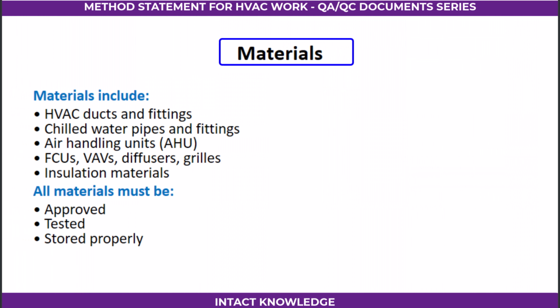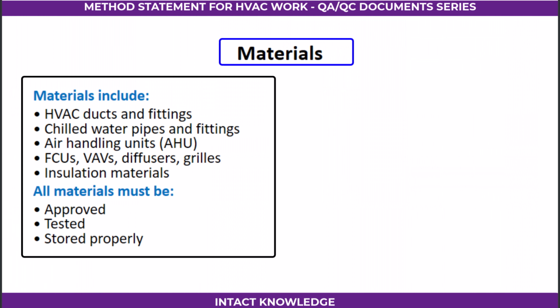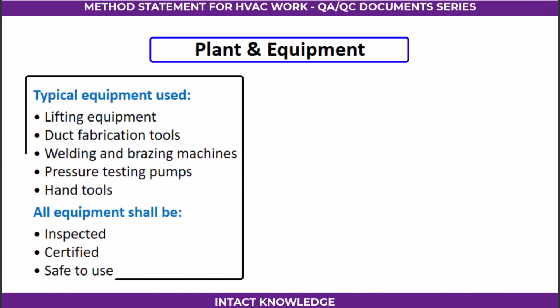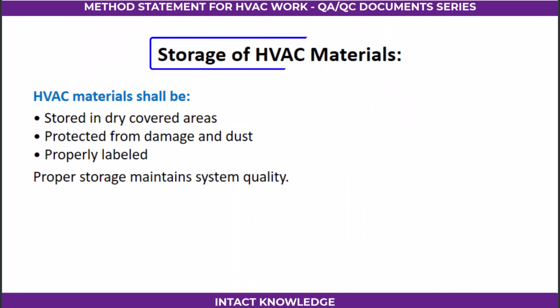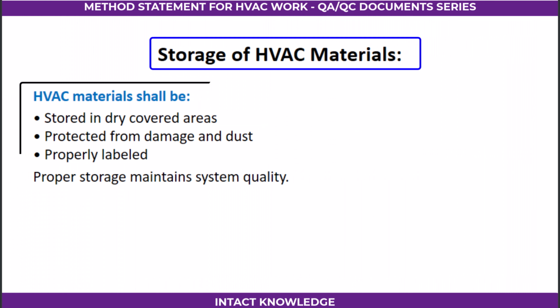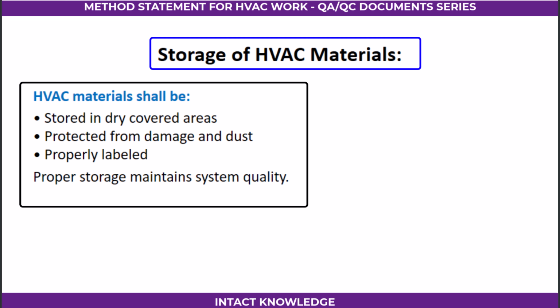Materials include HVAC ducts and fittings, chilled water pipes and fittings, air handling units, FCUs, VAVs, diffusers, grills, insulation materials. All materials must be approved, tested, stored properly. Plant and equipment. Typical equipment used: lifting equipment, duct fabrication tools, welding and brazing machines, pressure testing pumps, hand tools. All equipment shall be inspected, certified, safe to use. Storage of HVAC materials. HVAC materials shall be stored in dry covered areas, protected from damage and dust, properly labeled. Proper storage maintains system quality.